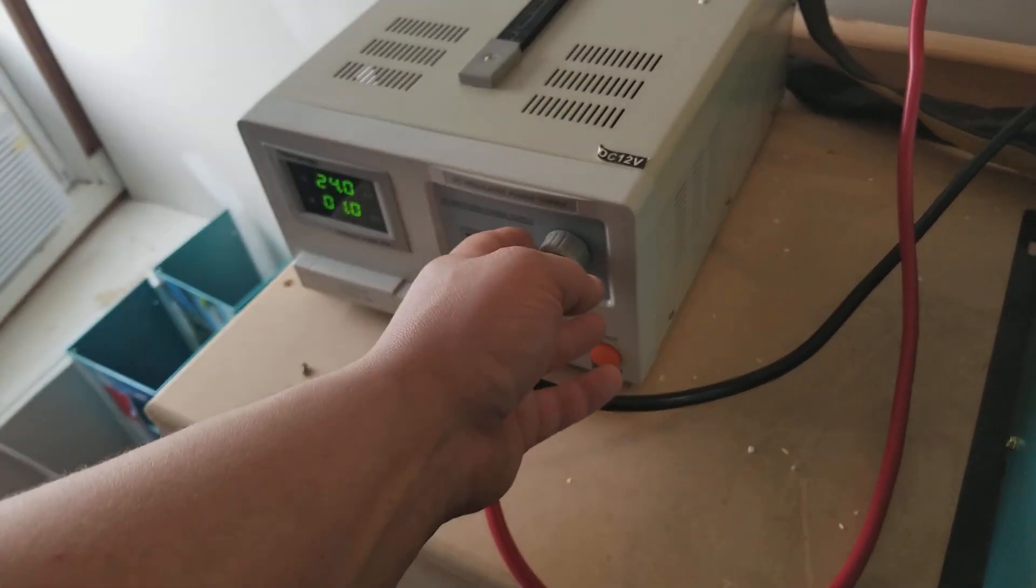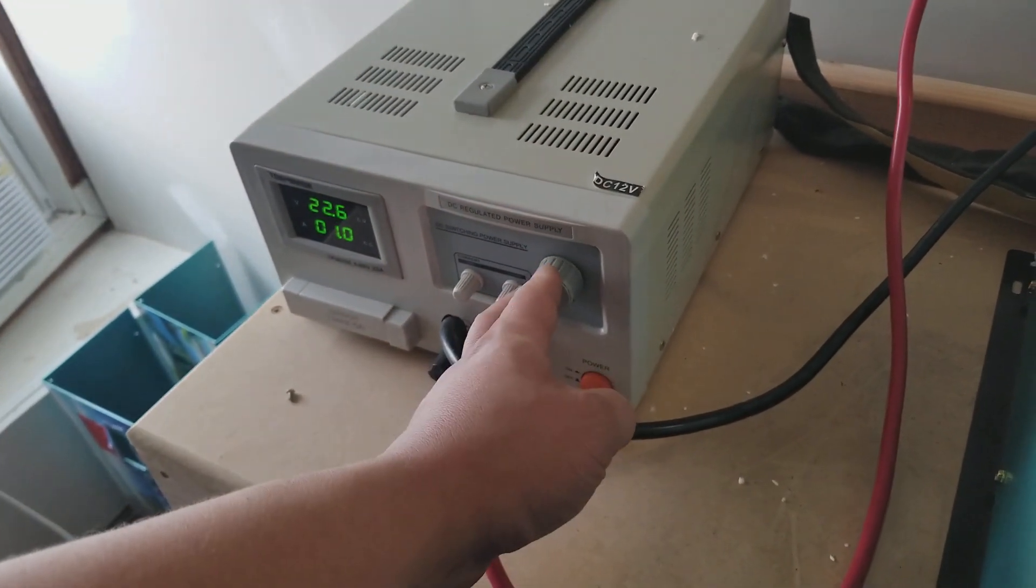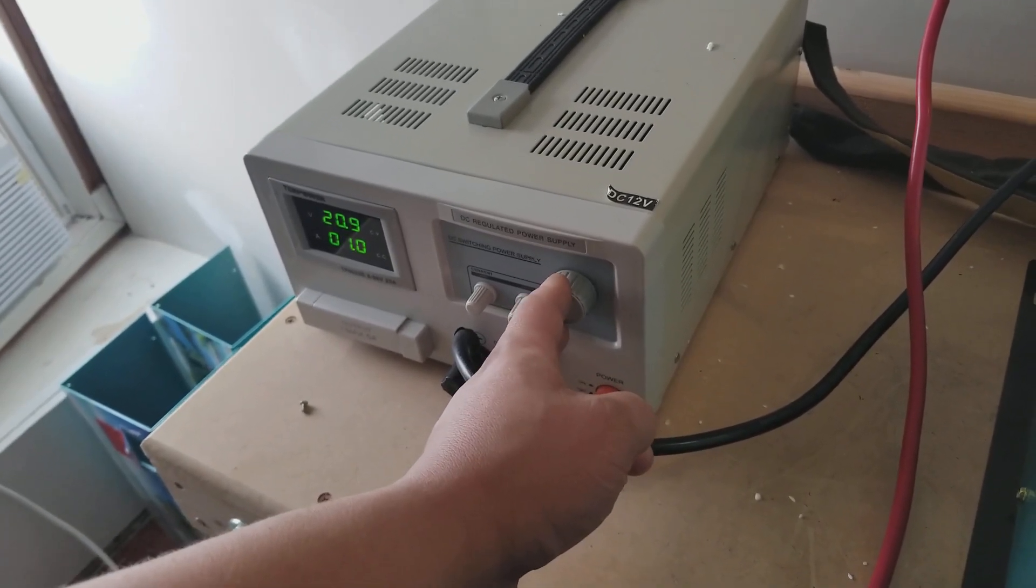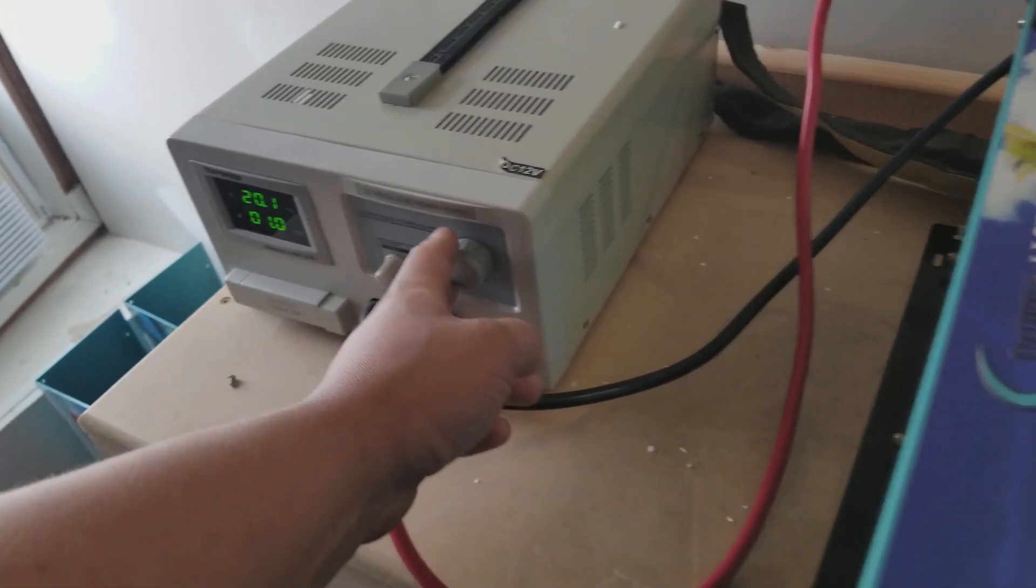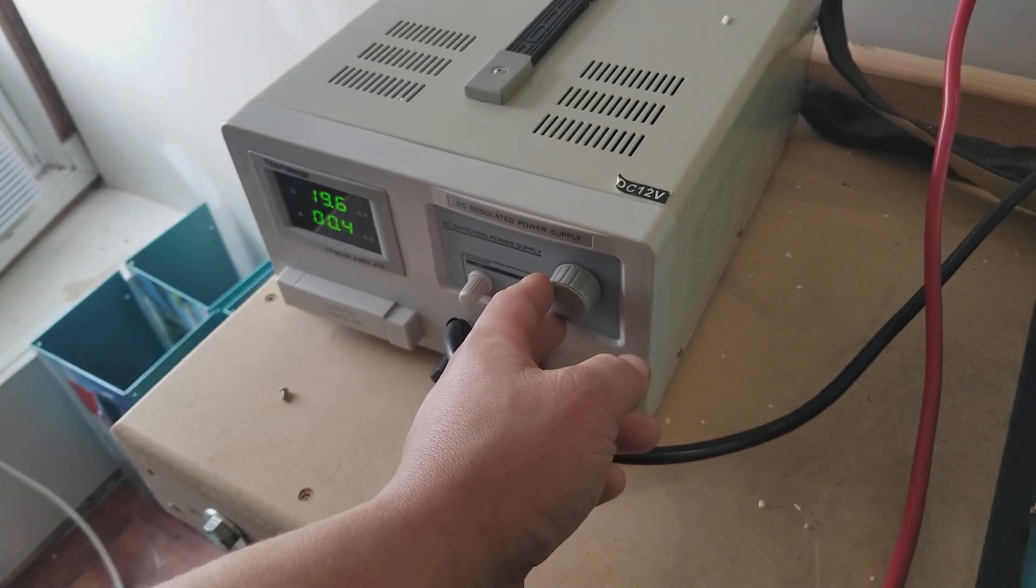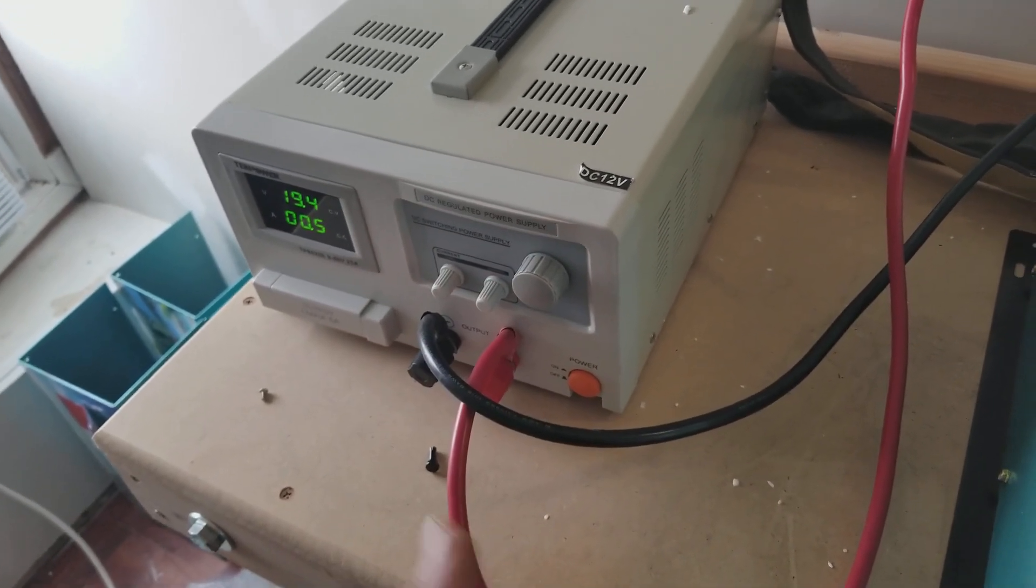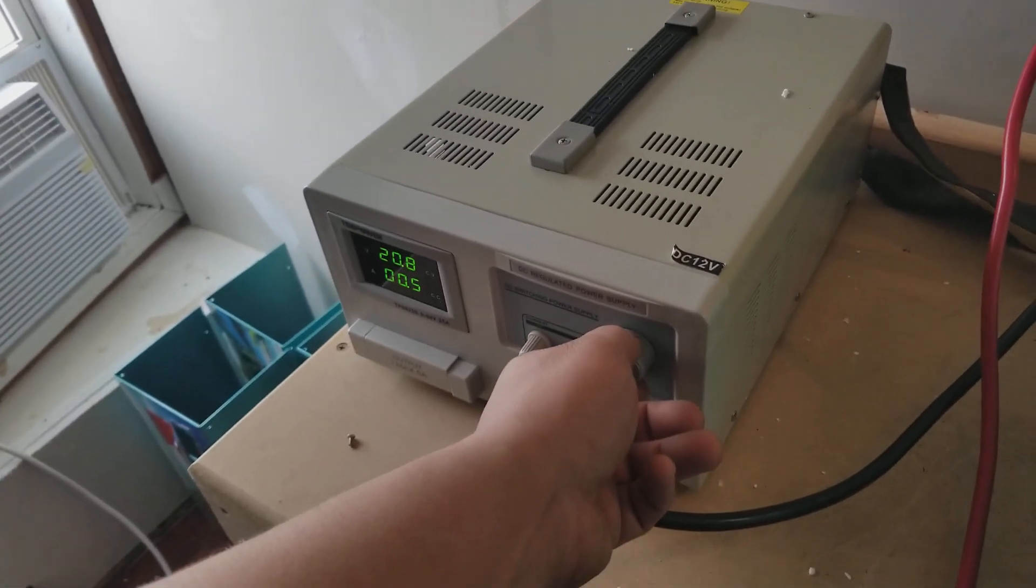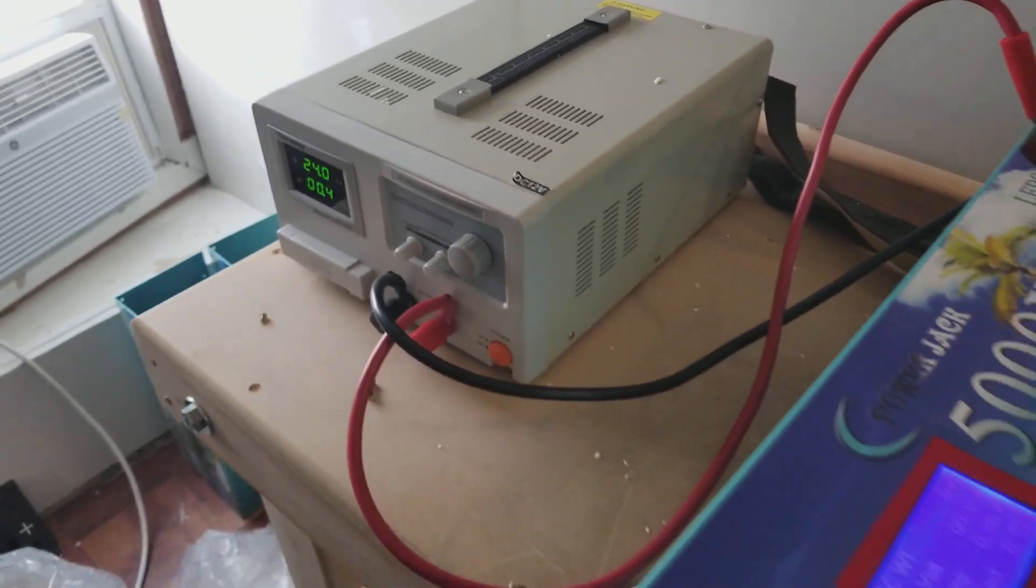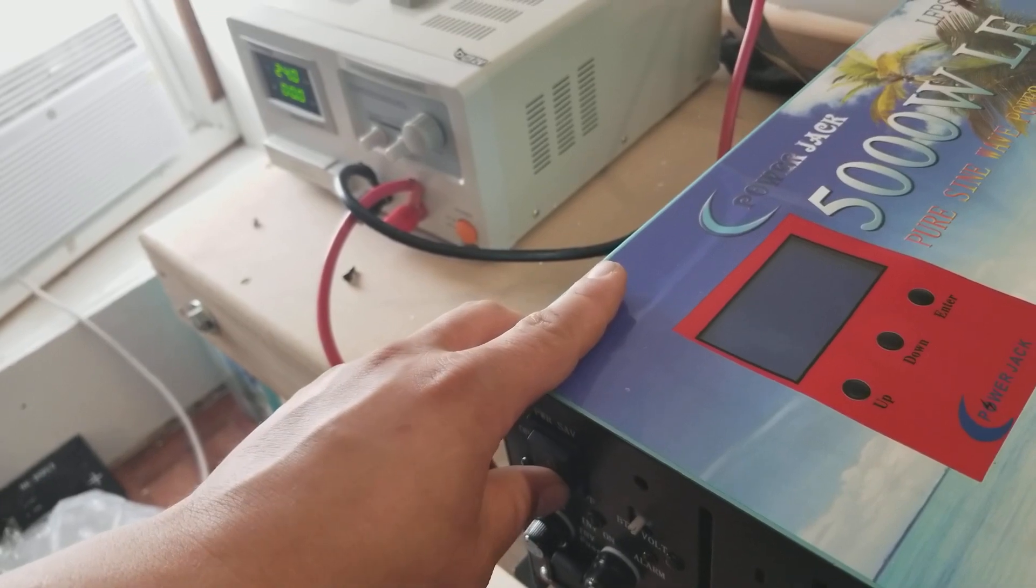Of course you get an alarm at about 20 volts, and then it shuts down. So right there, the inverter isn't able to handle that. We'll go ahead and bring it back up to 24 volts. Has to be reset because it shut down due to failure.